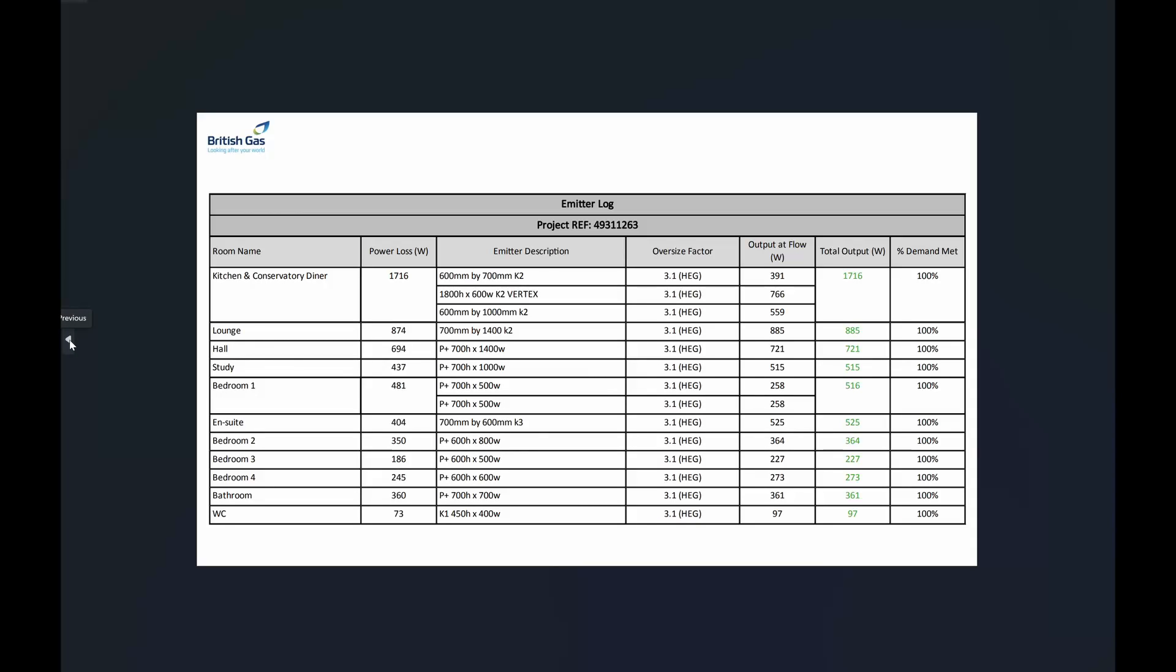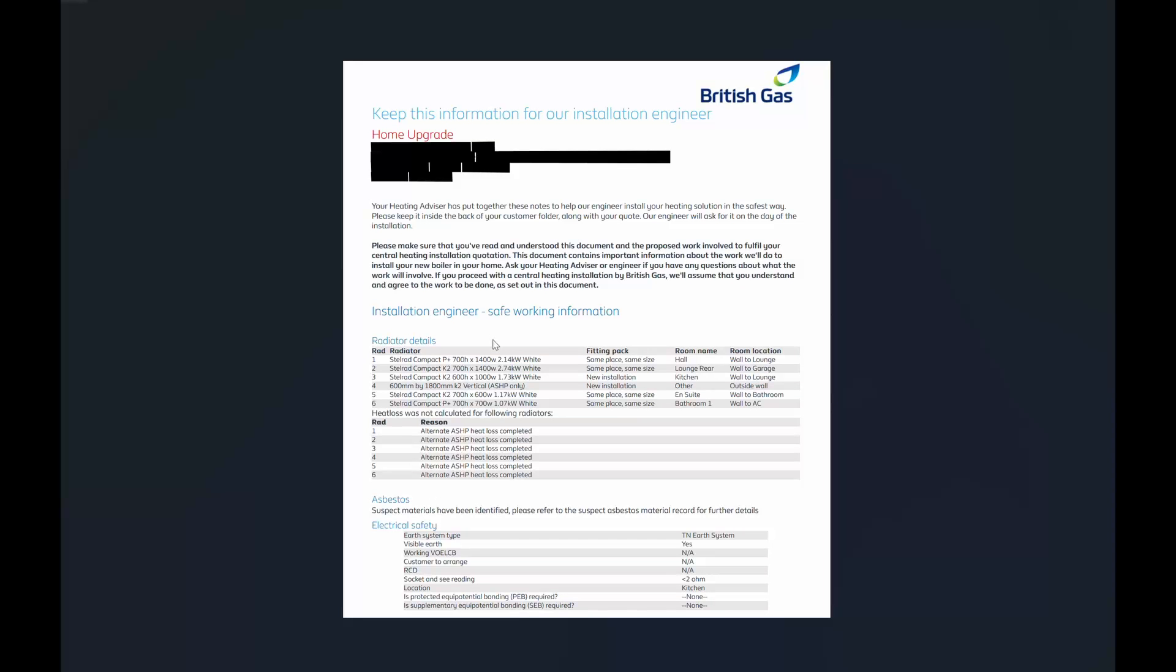You probably could have told that if you ever came in our house and went in there anyway because it was always like a furnace. So there were some further changes and a lot of debate about how we tackle some of these areas like the kitchen and the conservatory, the hallway. They decided that it required a much larger one and that was to account for a small utility area that is off the hallway that we leave the door open all the time, and the upstairs landing, both of which don't have their own radiators in. So to account for the heat loss we kind of opened the hall up, accounting for three areas. So I had upgraded the radiator in the hallway already but we needed to upgrade it further to account for those extra areas. You can see ultimately the demand is met with those planned radiators and eventually we changed what was happening in the kitchen and conservatory to kind of try and streamline things. Instead of putting three radiators in there we just put two in.